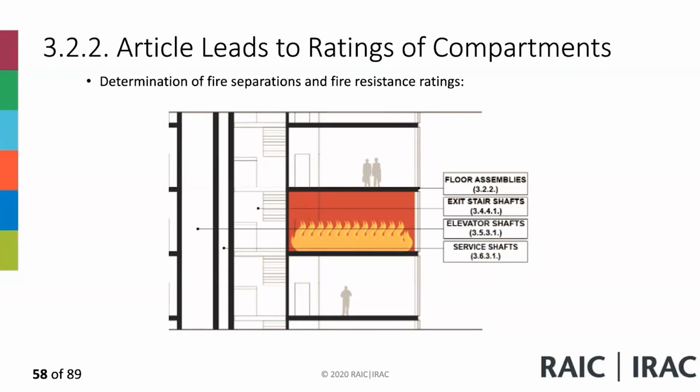So if we look at the building classifications, the articles under 3.2.2 subsection give us ratings of compartments. So it gives us floor ratings. And based on the floor ratings, we know the rating of exit stairs, service shaft, and elevator shaft.